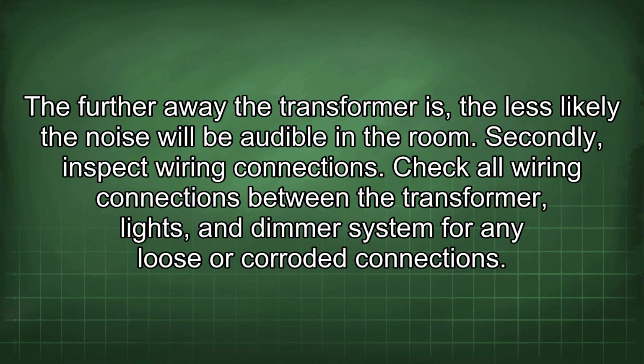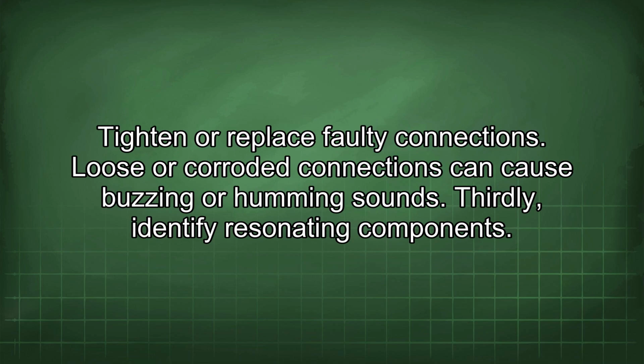Secondly, inspect wiring connections. Check all wiring connections between the transformer, lights, and dimmer system for any loose or corroded connections. Tighten or replace faulty connections. Loose or corroded connections can cause buzzing or humming sounds.